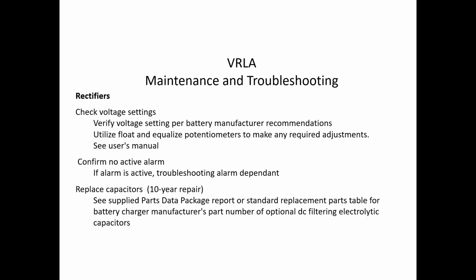Thresholds, I don't know if they're checking the alarm set points. Usually they're set up from install and they don't deviate from there, but you either have a high voltage alarm, a low voltage alarm, and those are usually indications or set points for the DC output of the rectifier. They can be checked and verified, but again, they're not usually done as part of a routine. They're usually done at install.